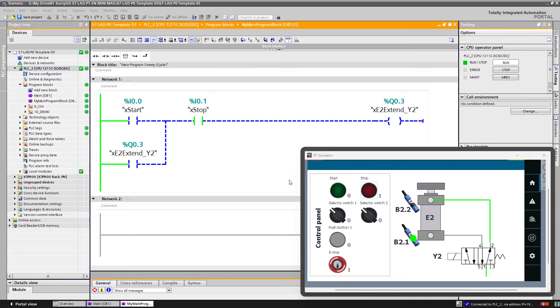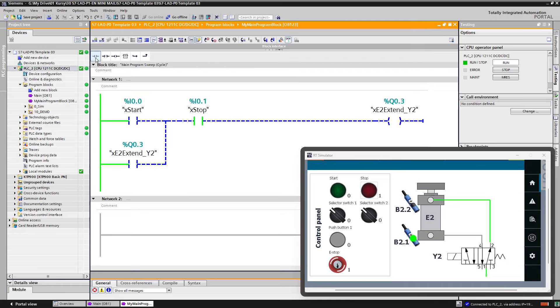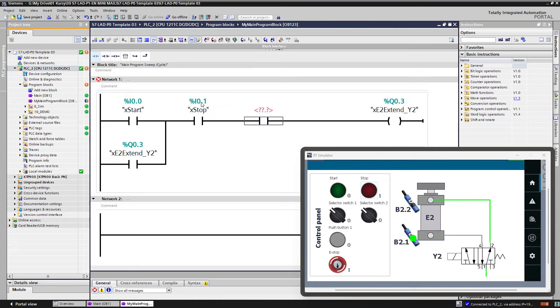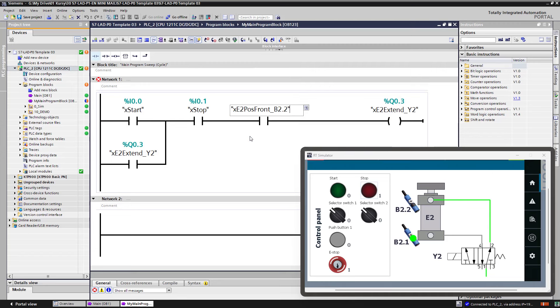So we have to insert into our code, into our diagram signal from the sensor B2.2, the front limit switch. This signal should de-energize the coil. So it should be placed in series to the other signals that will stop energizing the coil. For example, stop button. Let's assign here the operand the variable signal X E2 position front B2.2.